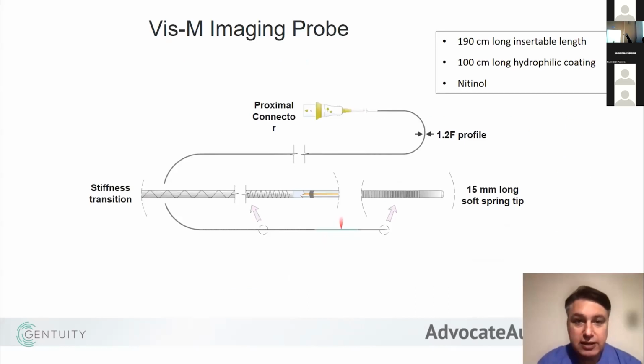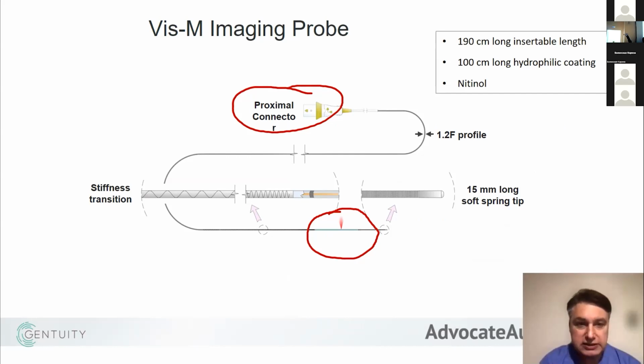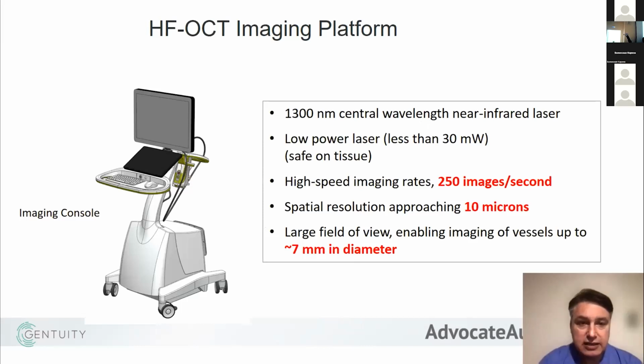So this is a little more detail of how there's a leading edge, and then you can see here the area where the light source will basically be pulled back. So this is kind of the window on the wire that has a light source. Then when this area is connected to the pullback system, the whole thing just navigates through the blood vessel. You do lose access. So I'll show you a video of that. You can see here that when you pull back using this machine, the images are going to show here.